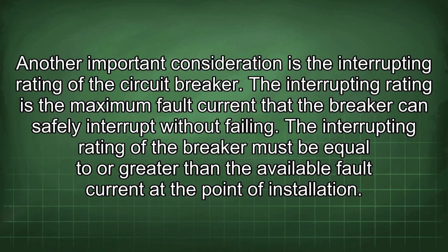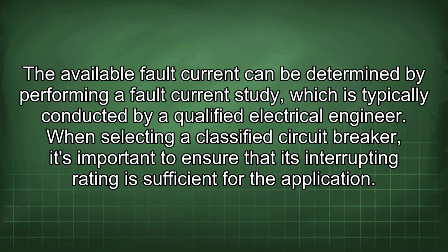Another important consideration is the interrupting rating of the circuit breaker. The interrupting rating is the maximum fault current that the breaker can safely interrupt without failing. The interrupting rating of the breaker must be equal to or greater than the available fault current at the point of installation. The available fault current can be determined by performing a fault current study, which is typically conducted by a qualified electrical engineer.